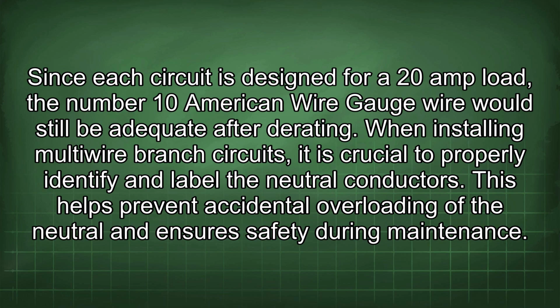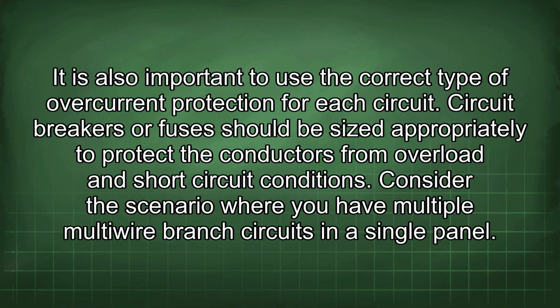When installing multi-wire branch circuits, it is crucial to properly identify and label the neutral conductors. This helps prevent accidental overloading of the neutral and ensures safety during maintenance. It is also important to use the correct type of overcurrent protection for each circuit.